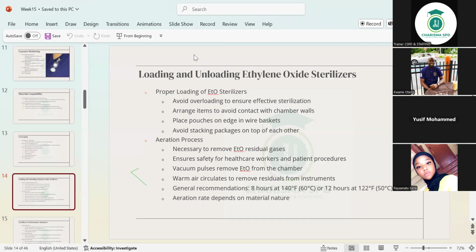Remember I mentioned condensation yesterday, right? And I've told you certain things this morning, that low temperature doesn't mean cold temperature. I said low temperature doesn't mean cold temperature. So you cannot pump cold air in there, because it's not cold in there. It's warm in there. It's not as hot as the 260, 270 that we use in the steam, but it's not cold. And so you cannot pump cold air in there because there's going to be condensation. All right? So warm air circulates to remove the residuals from the instruments.